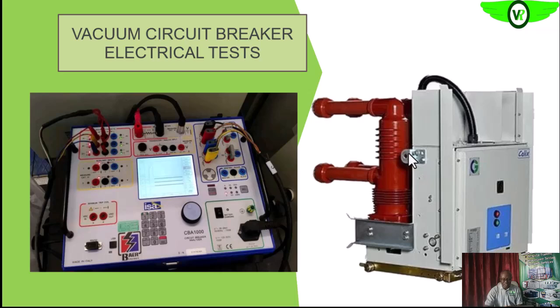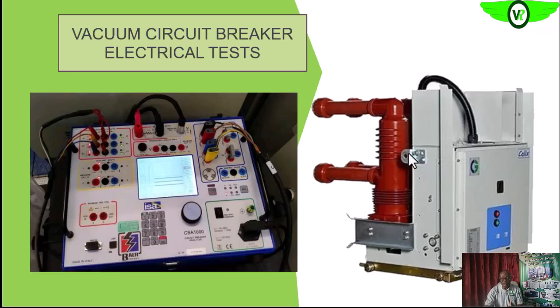The next that we are going to be looking at is the electrical test on the vacuum circuit breaker. So it's not different from what we have been doing. The basic test is as we had outlined earlier on others: the contact resistance test, the bolted connection resistance test with a low resistance meter, the milliohm meter, and then the insulation resistance test. Then we can also do the tan delta test, since we are looking at high voltage, to check the insulation.